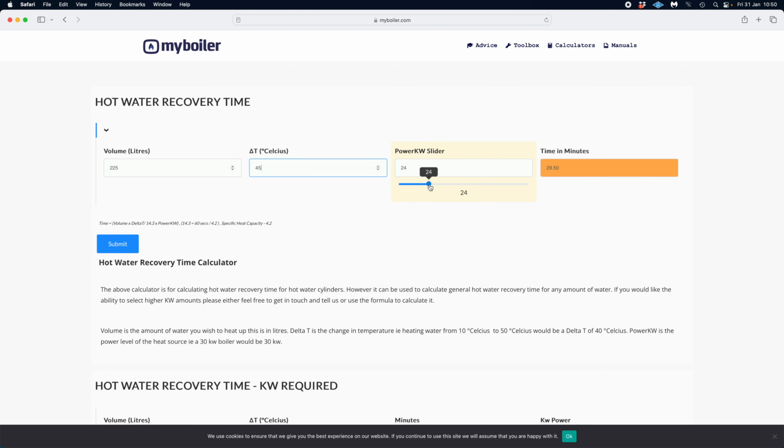But we've only got an 8 kilowatt or maybe even a 6 kilowatt heat pump. 6 kilowatt heat pump. So even overnight with hot water setback, it's going to get recovered fully in 118 minutes. So I think people tend to over egg all these requirements, but you need to make sure that, as we just explained, your hot water cylinder has a 6 kilowatt coil. Doesn't matter if it's slightly higher, but as long as you match those, these are going to be the recovery times that you've got. Now, there's a couple of caveats here that I like to discuss with these.